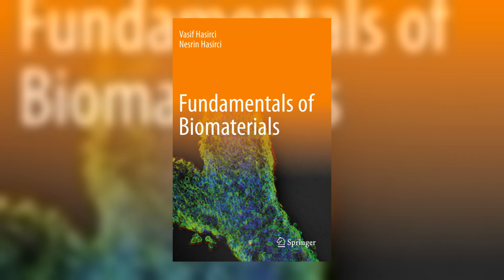Before you can bound what a material does to the body, you must know what the material is and what it can release. That is the whole of chemical characterization, the standard ISO 10993 Part 18. It sits first in the biocompatibility chain because biological risk factors as hazard times exposure, and characterization supplies the exposure term, the inventory of constituents, residues, and leachables that every downstream test, systemic toxicity, sensitization, then genotoxicity, tries to bound.